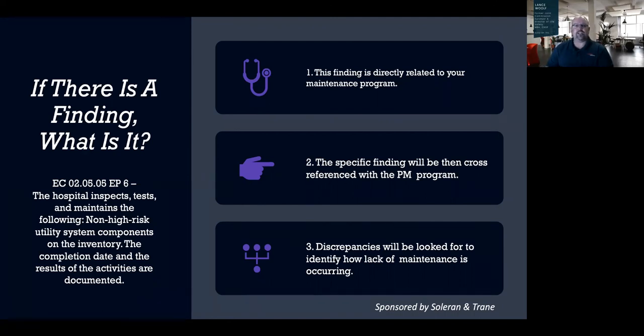So, some suggestions. As I said, this finding is directly related to your maintenance program, because there's nothing specifically in Environment of Care or Life Safety that identifies your chiller system. That's another common question I got when we were walking through: people ask, hey, there's nothing specific. They talk about generators and ATS switches, those are specifically identified in EC and LS standards, but the rest of the plant isn't. And so that's where that question came from: where else does this finding come from? And that's specifically what it is, 2505 EP6 or 2505 EP5.